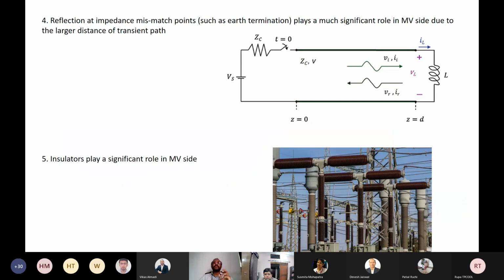Now, when I say HV side, with respect to the LV side, it is essentially the medium voltage side. When you consider that side of a transformer, the reflection effects become more significant, because there is a long distance that the voltage waveform will travel back and forth. And also, the insulators play a significant role on the MV side compared to the LV side, because on the LV side, we are more interested in surge protection rather than the insulators when it comes to transients.